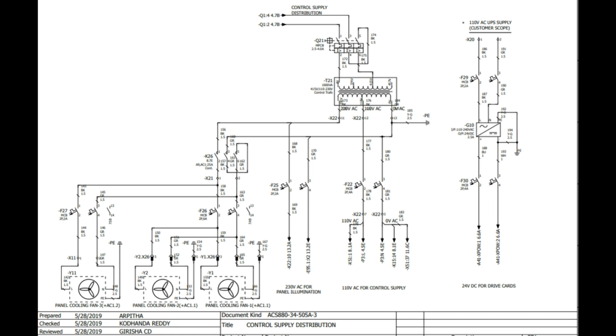Coming to the left hand side, that is for 230 volt, the very first tapping you can see is for F25, that is an MCB again, and it is used for panel illumination, CFL and different lighting equipment. Next, it is K26, so it will feed two different MCBs. One is F26 and another is F27. Both are used for panel cooling.